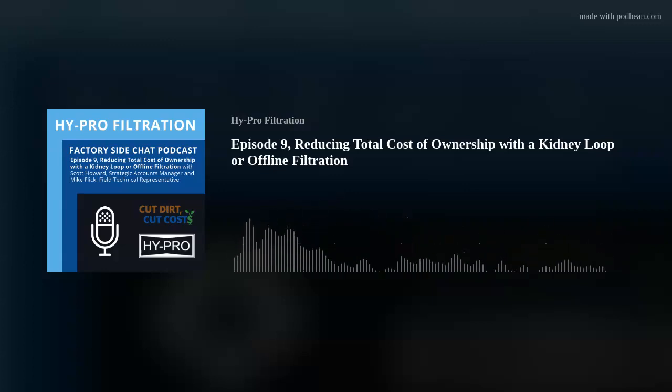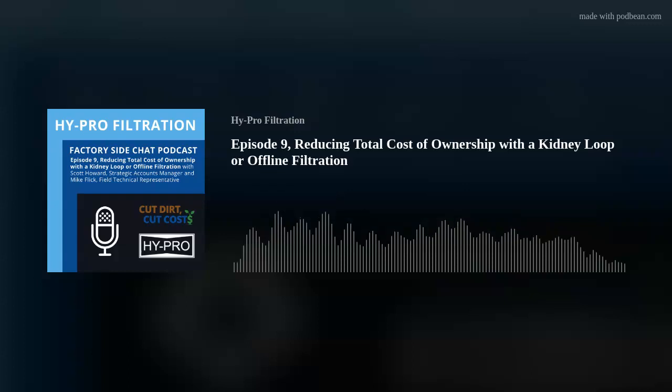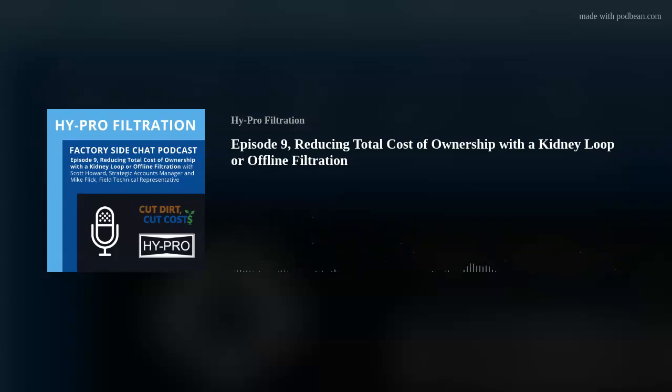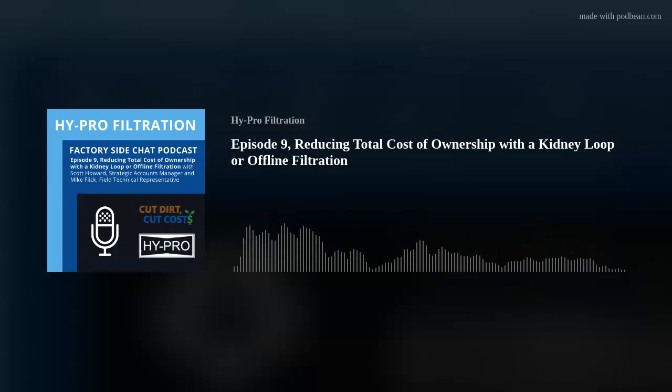So, one of the beautiful things about either an online or an offline kidney loop is it allows you to put a third party, for lack of better term, to do the work of cleaning the oil for you. So when I put a kidney loop in place, not only does it continually polish the oil and lower the ISO codes, but in addition to that, it allows your current filters in the system to last longer. Because when you have cleaner oil, your filters have less dirt to catch. So if they have less dirt to catch, then they're going to last longer over time.